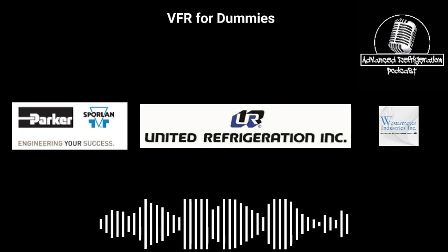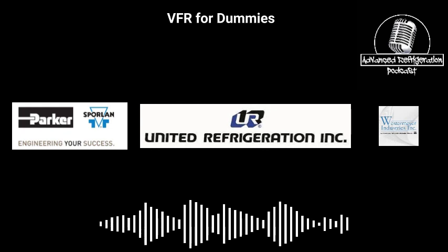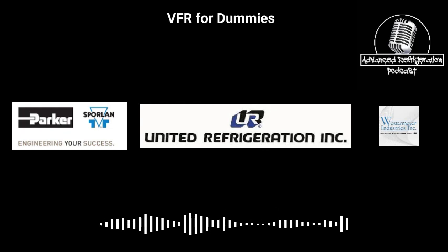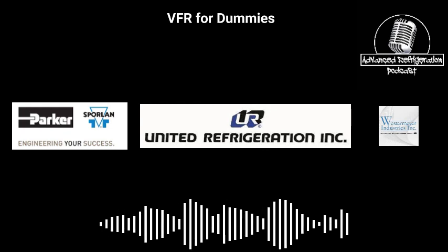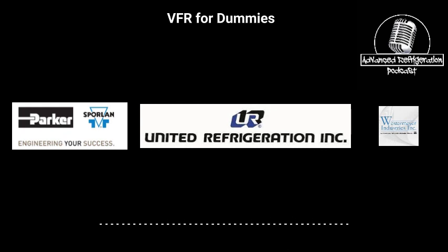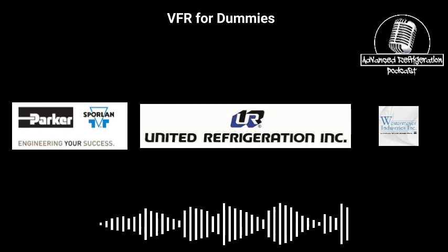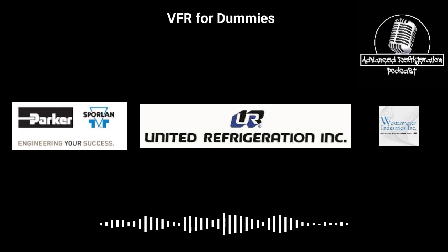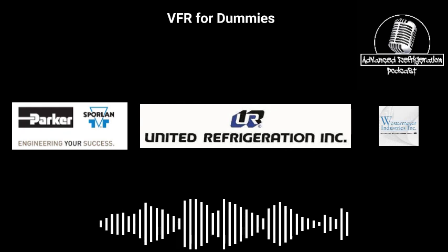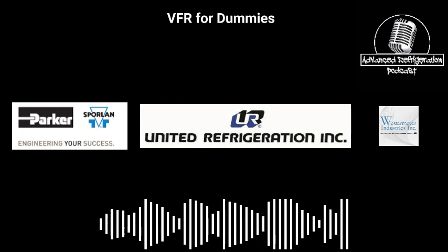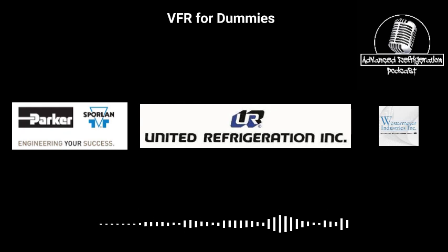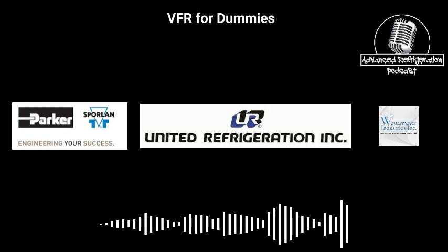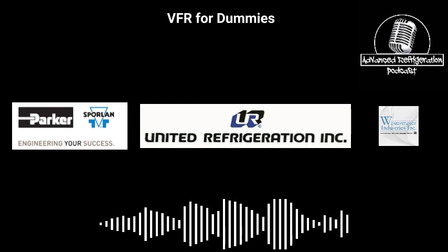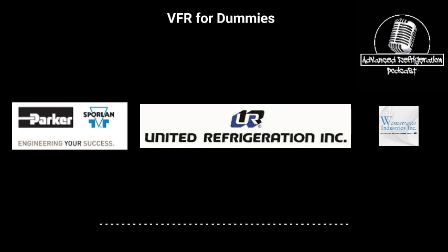To a degree, yeah. The service tool does give you a lot of information. And like I said at the beginning, it's really just going back to the basics. The service tool, is that the program you use to connect to the Daikin's? Yeah, it's called a service checker. Okay. It just plugs in on the same communication line and gives you all the information, all of the sensor values in the outdoor unit, the indoor unit temperatures, valve positions. The only thing it doesn't give you is branch selector information.